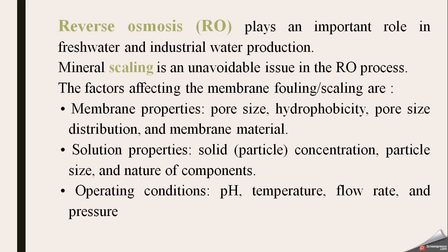in affecting the membrane fouling or scaling are basically membrane properties: pore size, hydrophobicity, pore size distribution, etc., and also the type of membrane material. The second important factor is the solution properties, that is the water which needs to be cleaned. The solid particles, concentration, particle size, and nature of compounds which are present in the solution or in the water need to be considered and play an important role in the fouling or scaling.